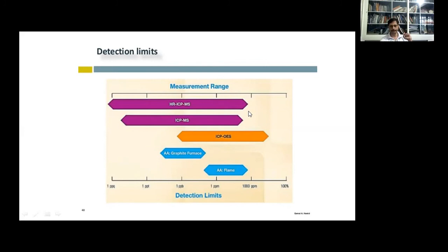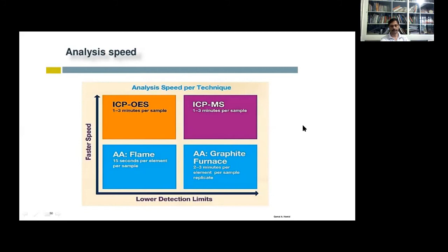If you are talking in terms of analysis speed, here speed will be faster, here detection limit will be lower. ICP-OES and MS both have an analysis speed of 1 to 3 minutes per sample. Atomic absorption spectroscopy, where flame is used, 15 seconds per element per sample is the speed. Atomic absorption spectroscopy, where graphite furnace is used, analysis is still slower. It requires 2 to 3 minutes per element per sample replicate.